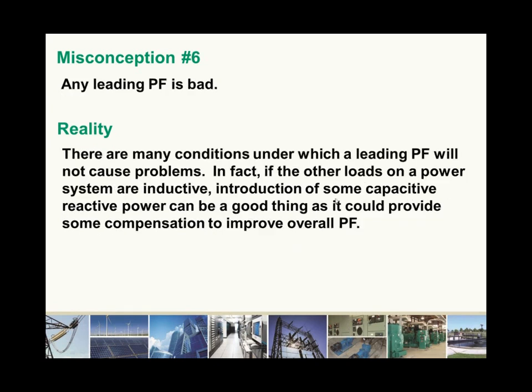And then the final misconception is simply that any leading power factor is bad. In reality, there are many conditions under which a leading power factor will not cause problems. In fact, if the other loads on a power system are inductive, introduction of some capacitive reactive power can be a good thing, as it could provide some compensation to improve overall power factor.